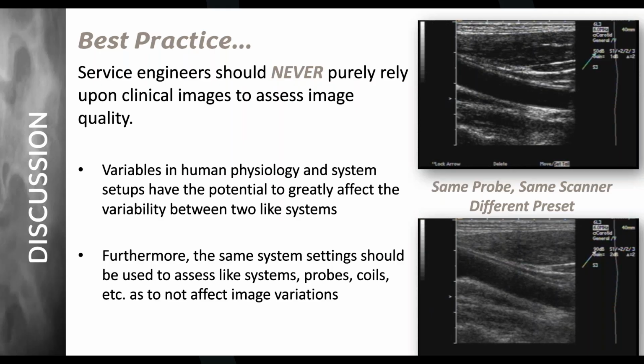Yeah, so we recommend service engineers should not rely on the clinical image to assess the quality of that system. And this is why you see these two images. That's actually me. This is my common carotid artery here. You can see how clear that is. Years of clean living. You're right. But that's why. If you use different presets, your image quality is different. By using a Phantom, you're getting that consistency from test to test.